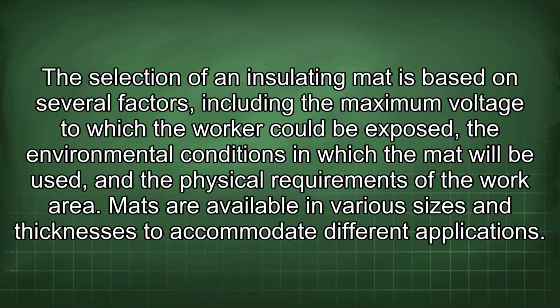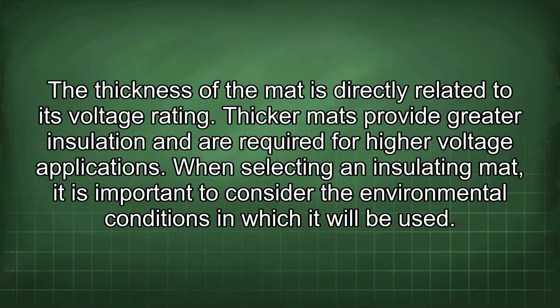The selection of an insulating mat is based on several factors, including the maximum voltage to which the worker could be exposed, the environmental conditions in which the mat will be used, and the physical requirements of the work area. Mats are available in various sizes and thicknesses to accommodate different applications. The thickness of the mat is directly related to its voltage rating. Thicker mats provide greater insulation and are required for higher voltage applications.